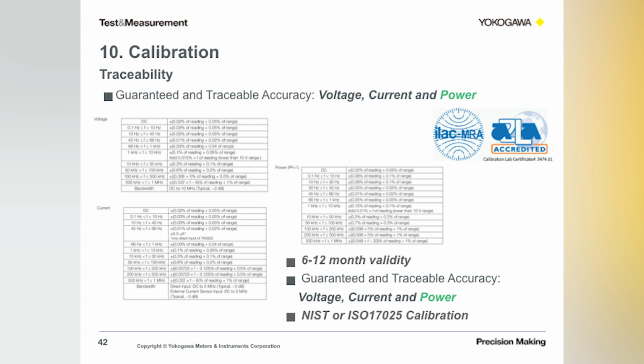There are other standards also that are related to defense and aerospace industries, but even for those industries, sometimes ISO 17025 is very commonly accepted. Yokogawa provides calibration and traceability to both these standards. In fact, our calibration lab is certified to the A2LA standards, and it is located in the Newnan, Georgia office. So all our instruments can be calibrated and guaranteed that way.